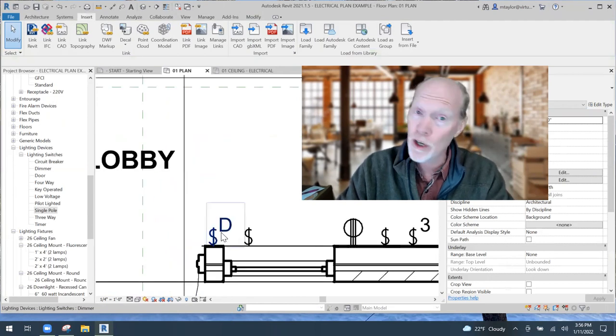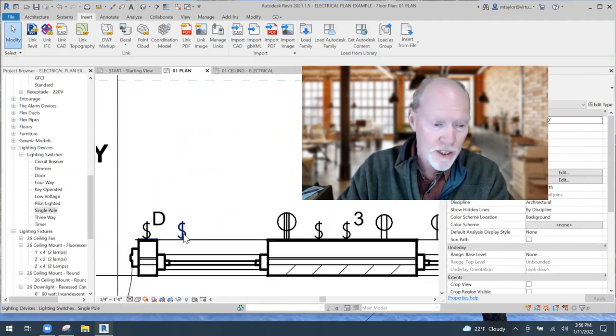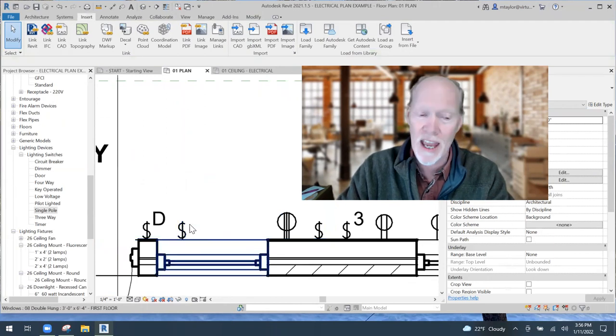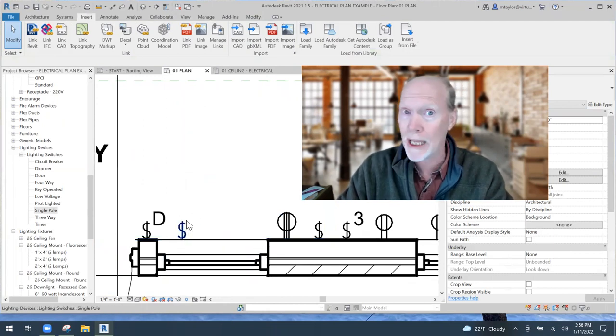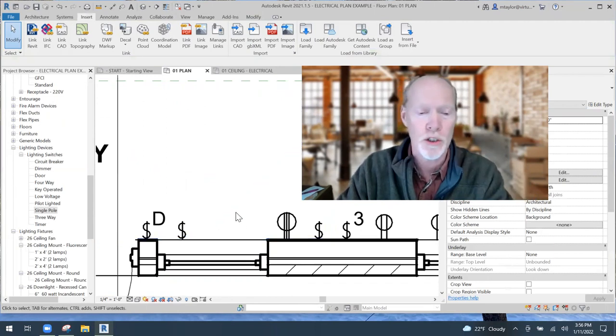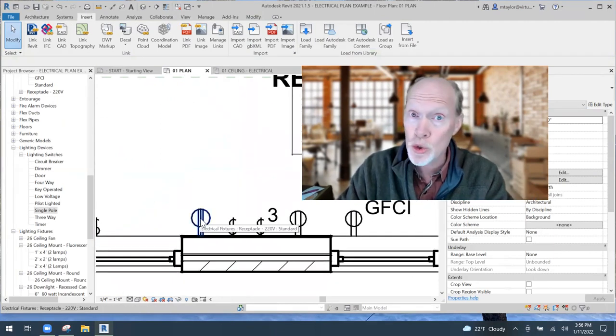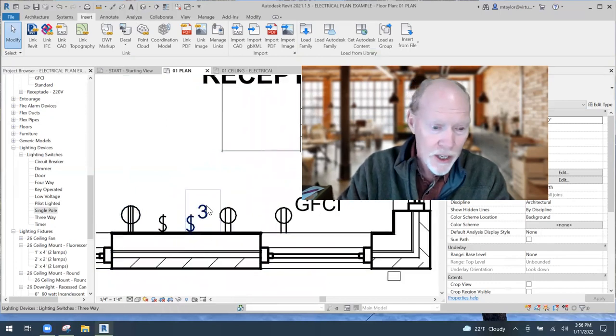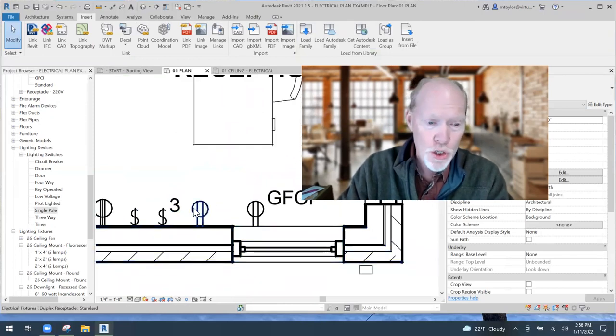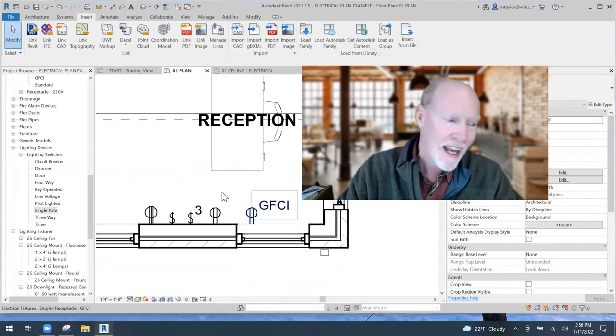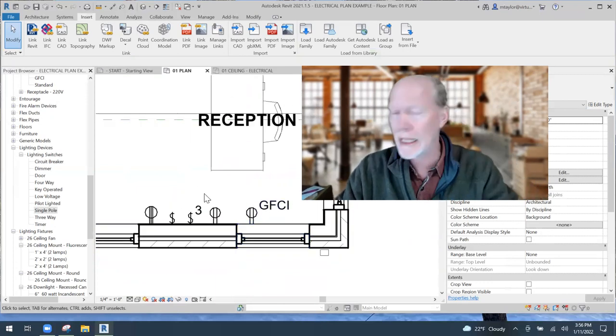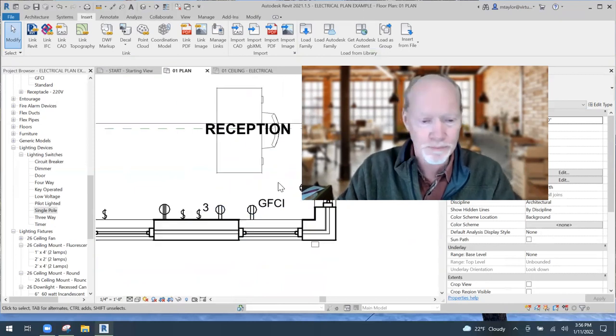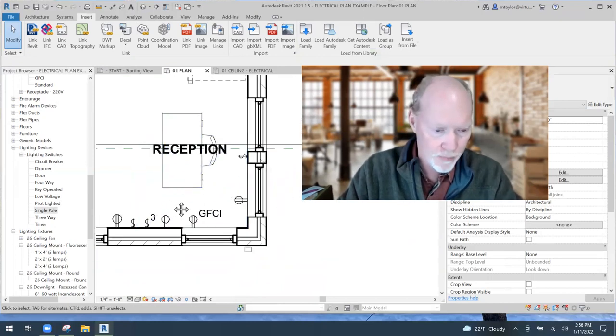The symbols that show up in plan: a big D is a dimmer switch; a lighting switch with no letter or number is a plain single-pole switch; 220 voltage has three vertical bars in it; a three-way switch has a 3; and a duplex outlet has two lines. A simplex would have a single line, but again, no one ever uses those.